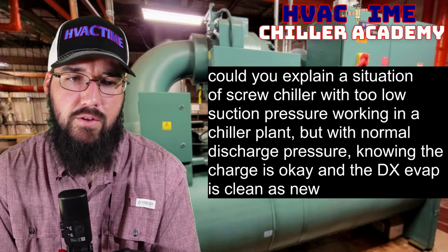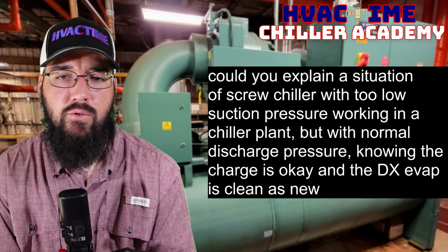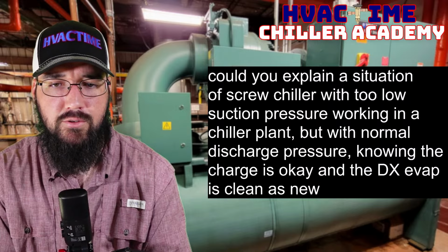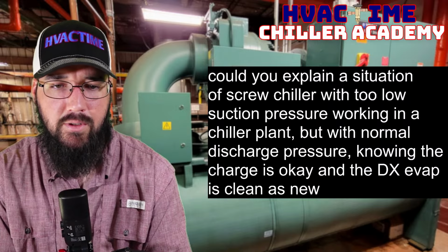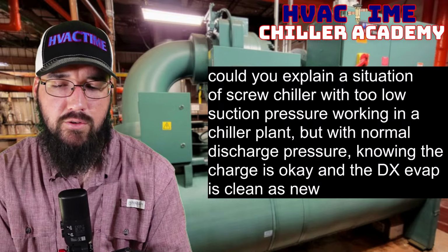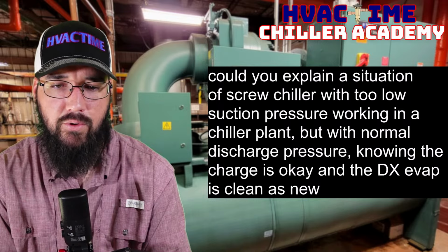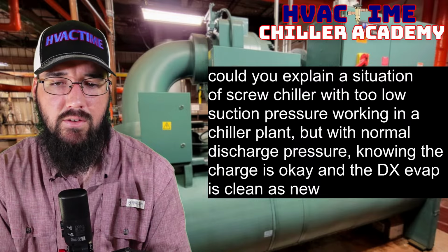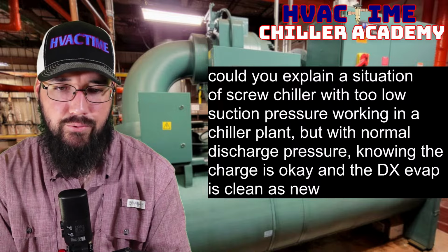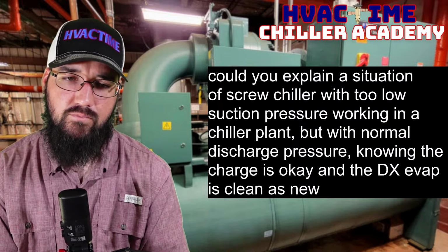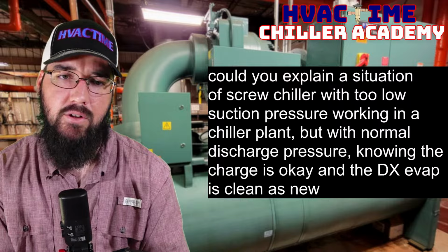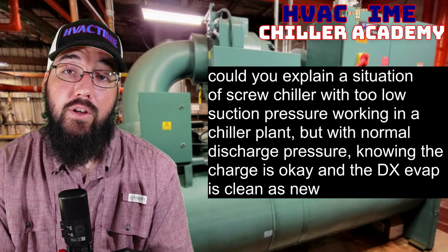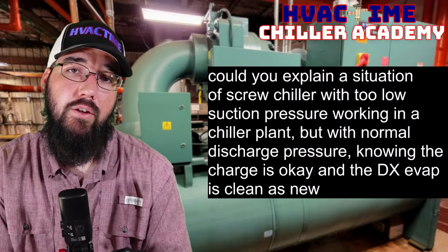Could you explain a situation of screw chiller with too low suction pressure working in a chiller plant, but with normal discharge pressure, knowing the charge is okay and the DX evap is clean as new? All right. Well, first I would question, what is too low? What are you calling too low?